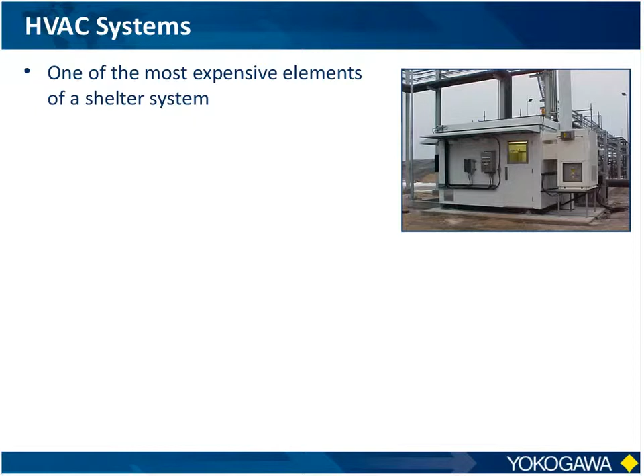For example, one of the things you want to be very careful about is to size it properly. Some pieces of equipment, like chromatographs, need a high amount of heat wattage during power up, but once they reach their operating conditions, the amount of heat or wattage needed drops tremendously. For example, it might need 1,400 watts during power up, but only 400 watts during normal operation.